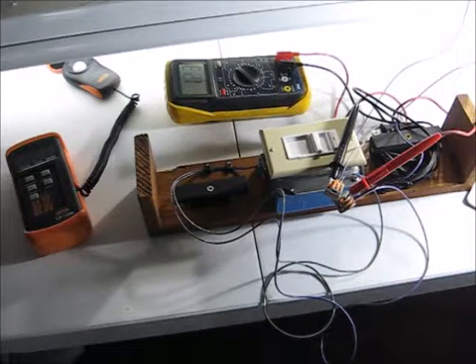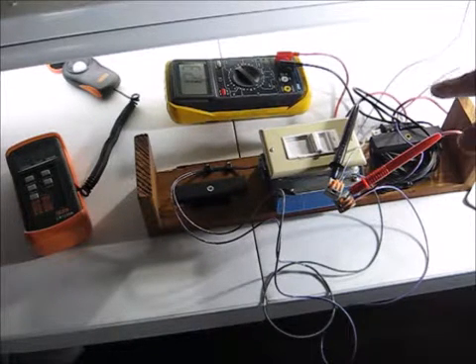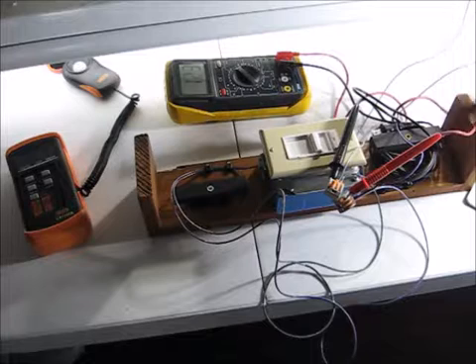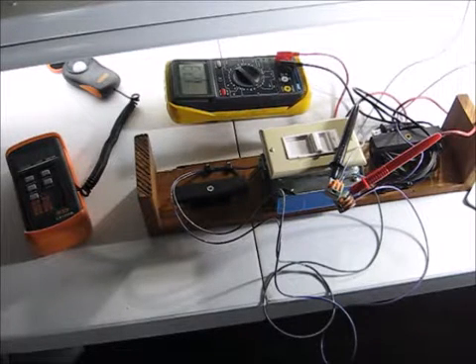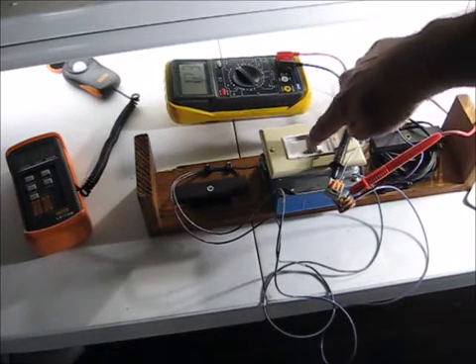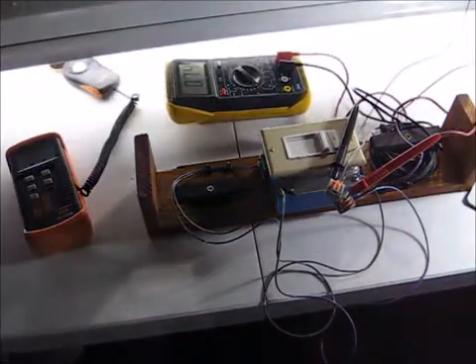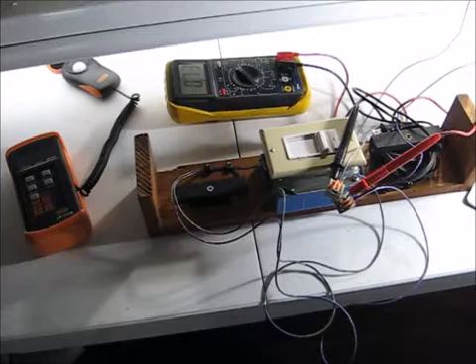So, we're going to graph these results using Excel, because I can't find my graph paper. And we'll examine the response of this ballast. It's important that you know, at what end of the range of 0 to 10 volts, the thing is maxed out and won't go any higher. And the same thing for the bottom when it's dimmed all the way. This is an American ballast. So, it is not going to want to dim to off.